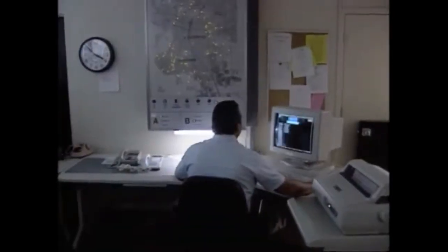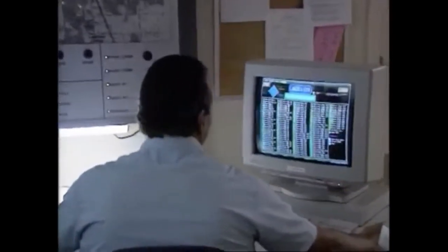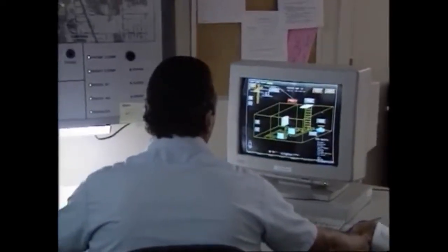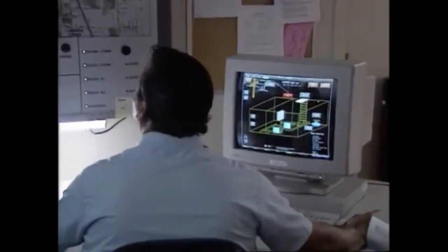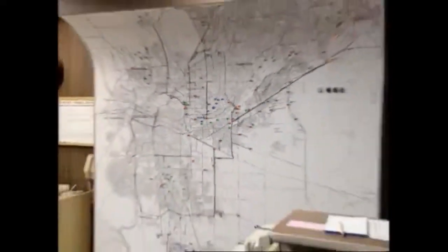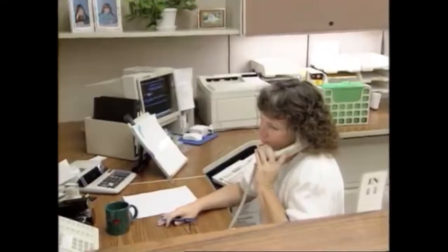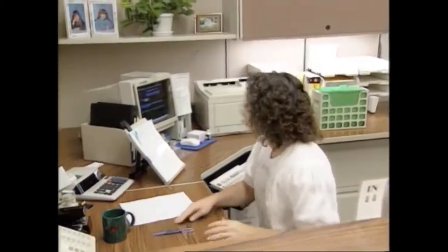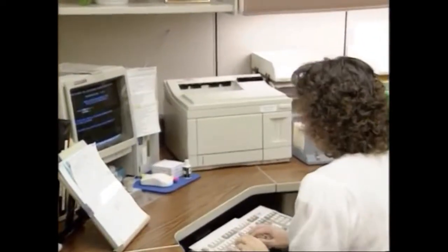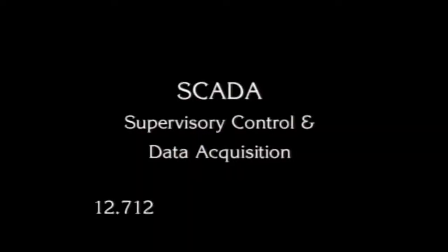A simple system may be nothing more than an annunciator board that signals the type of alarm and the station. More sophisticated microcomputers are now frequently used. They perform logging functions of such information as date, time, and nature of alarm. In some systems, the computer automatically polls the status of the lift stations in a predetermined sequence. If an alarm occurs, the computer can be programmed to automatically dial a pre-programmed number to a collection system operator and relay a message over the phone.